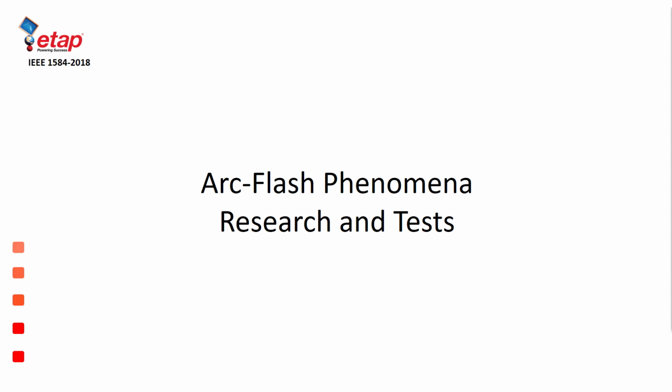First, I would like to go over the arc flash phenomena research and tests which were done by the IEEE and NFPA collaboration effort, which was started more than 10 years ago and which was managed by Dr. Wei-Jing Lee of the University of Texas Arlington, and how this new research and testing resulted in a collection of almost 2,000 tests which were used to develop the new model.